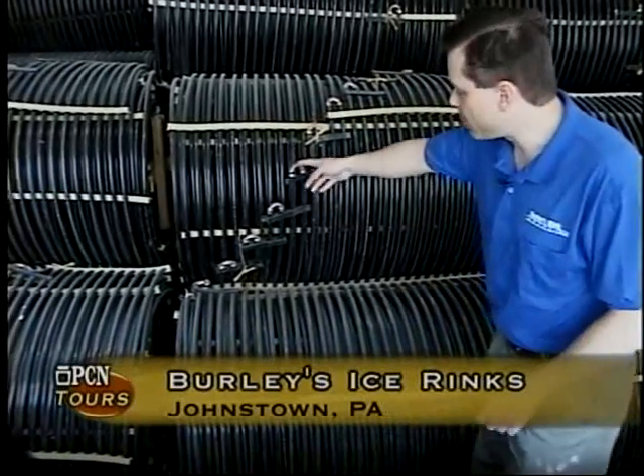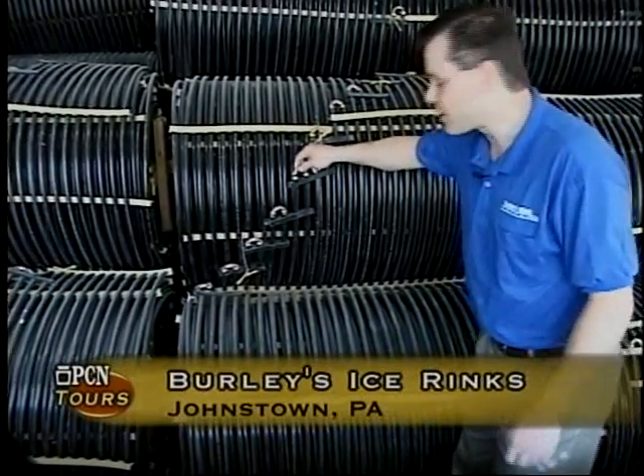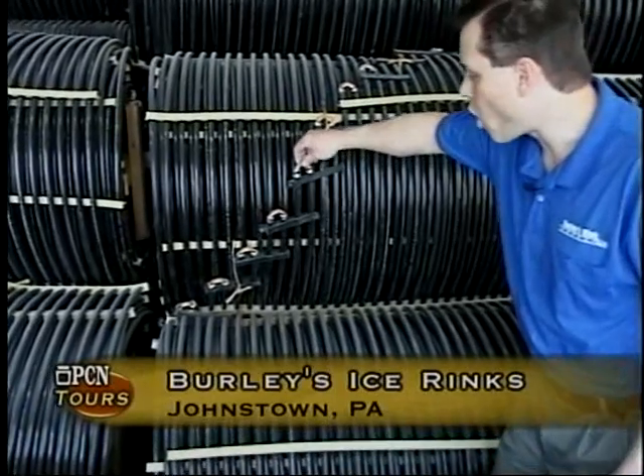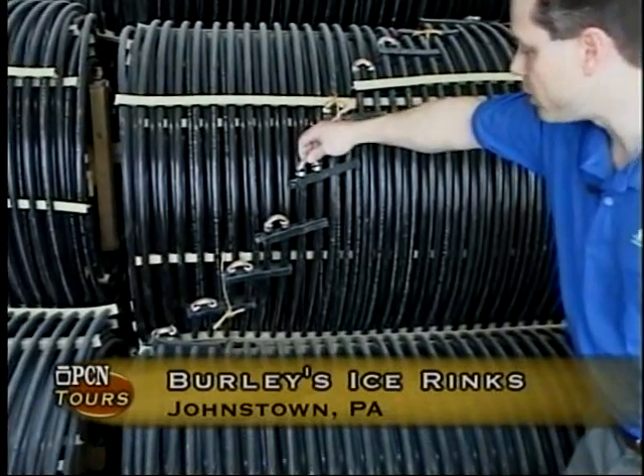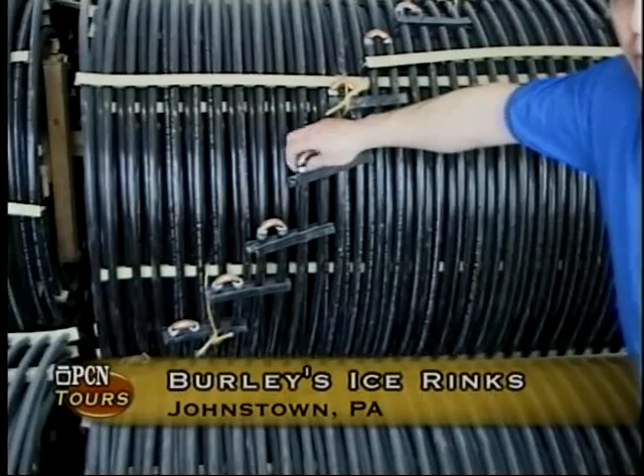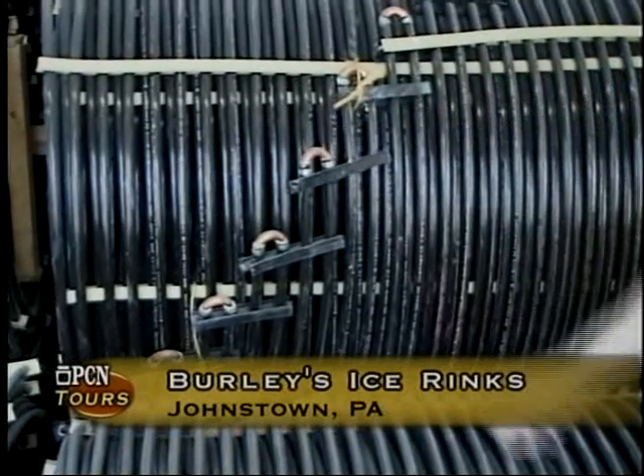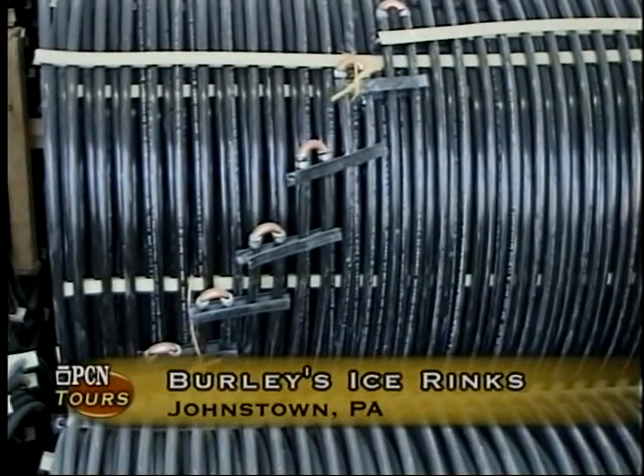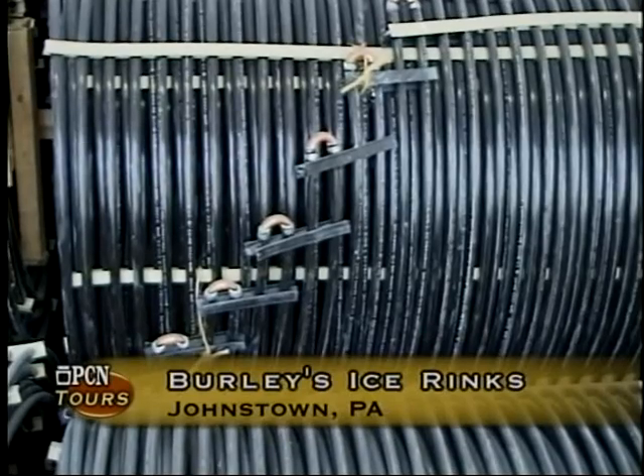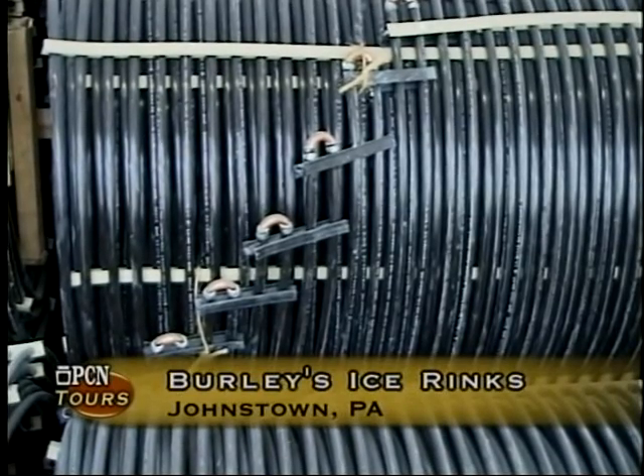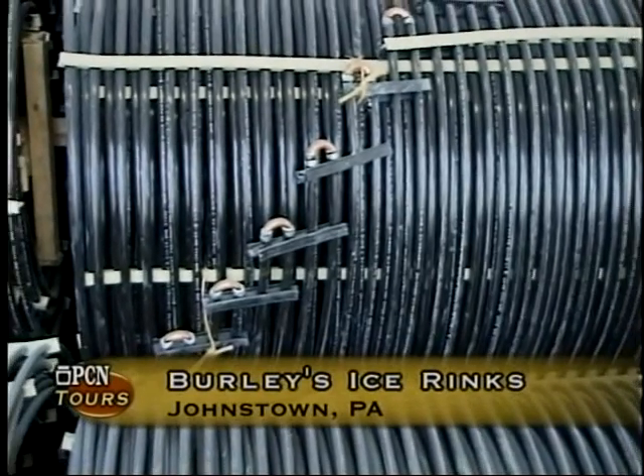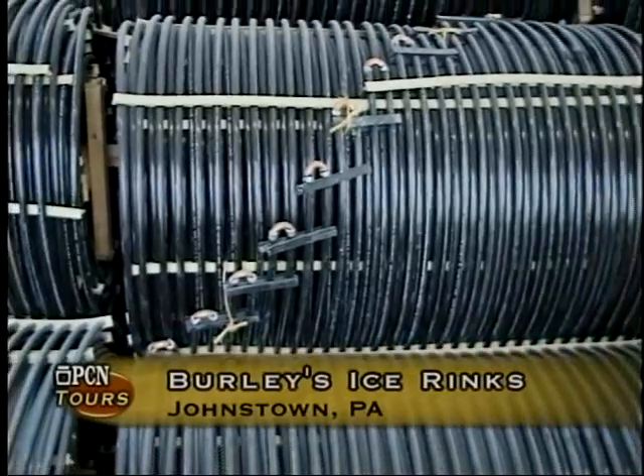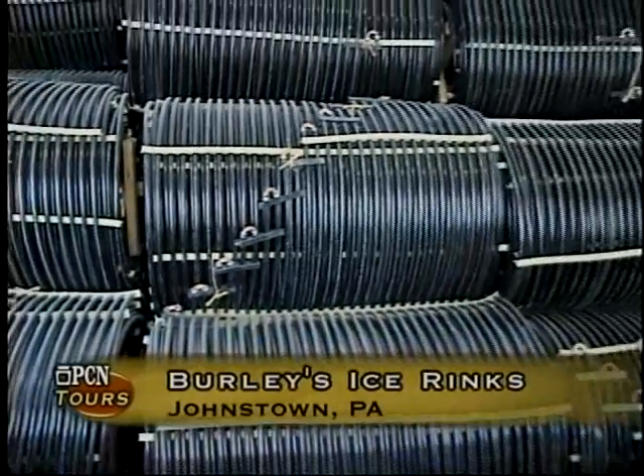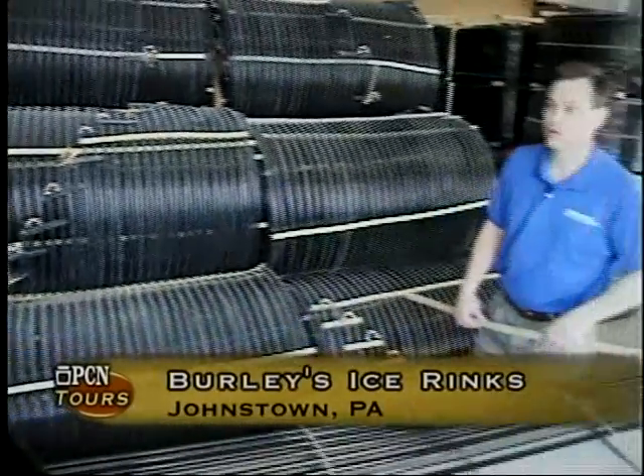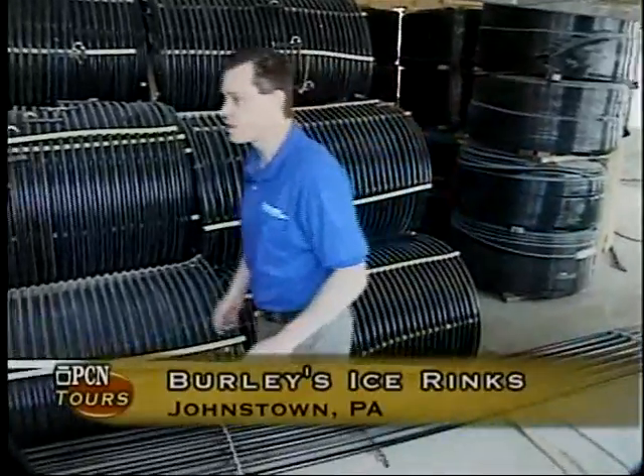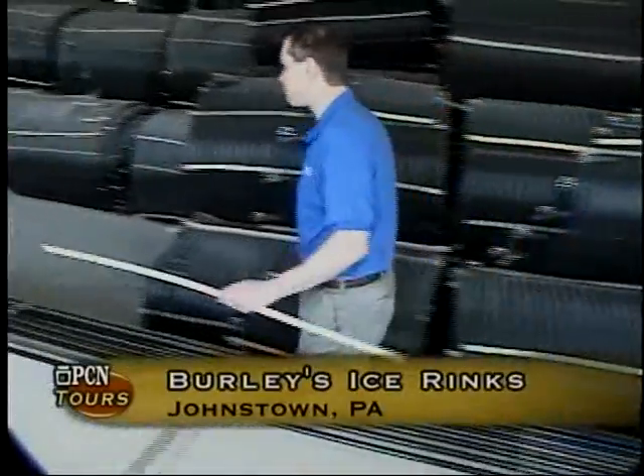The process of putting a U-bend in is pretty simple. We use a 17/32 OD hard copper U-bend that's made for us, and we insert it, and then we clamp it with 2 stainless steel pinch clamps, and it makes up the finished product. They're pressure tested, and they're ready to go, and they ship out in spools just like this, and they ship all over the world. We can show you down at this end how the process of putting the U-bends in takes place.